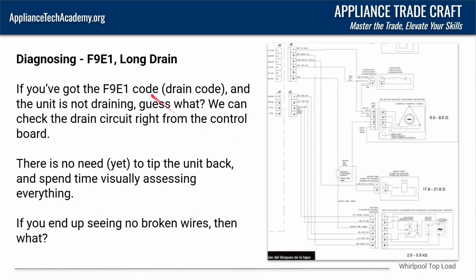So let's say we have an F9E1, which is a long drain. If you got that code and the unit's not draining, guess what? We can check the drain circuit right from the control board. There's really no need at this point to tip the unit back and spend a whole bunch of time visually assessing everything. Because what happens if you see no broken wires? Then what? You're kind of starting to replace parts and get a little frustrated.